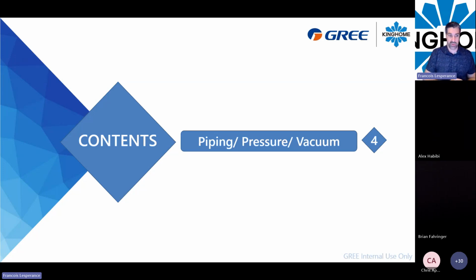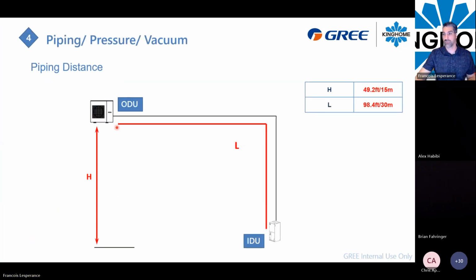So we will move forward with the piping, the pressure, and the vacuum. So as I said at the beginning, the maximum piping length you can have between the indoor and the outdoor unit is 98 feet. And also, in that example, if the condenser unit is installed on a roof, and then you have your indoor unit or your cased coil right here, the height will be 49 feet. And it can be reversed. So it can be the compressor on the ground and the indoor unit like 4 floors away, but 49 feet, the height difference, is the maximum.